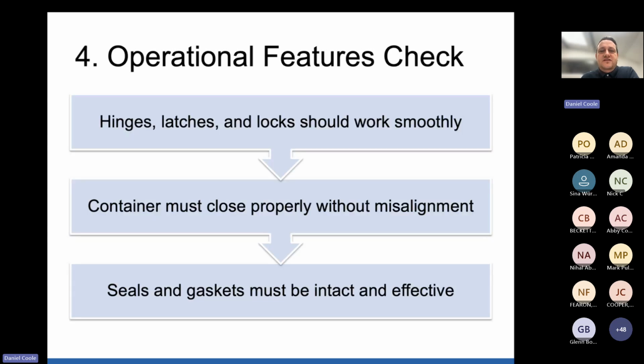Operationally, hinges, latches, and locks should work smoothly, and that's something you might need some maintenance on if these containers are being repeatedly cleaned and then put in autoclaves. Latches and locks could potentially get stiff, so some lubricant could help with that, and that's something you could speak to your manufacturer about. The container must close properly without misalignment, so it should align properly. Obviously, in the example of a damaged edge or corner of the container, that's not going to align properly. And seals and gaskets must be intact and effective.